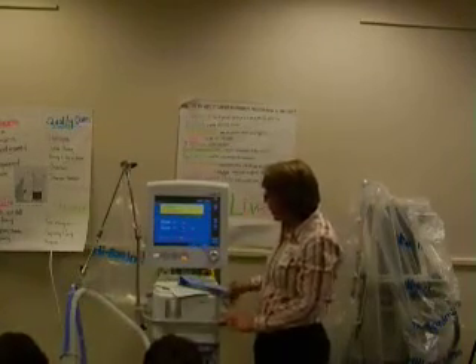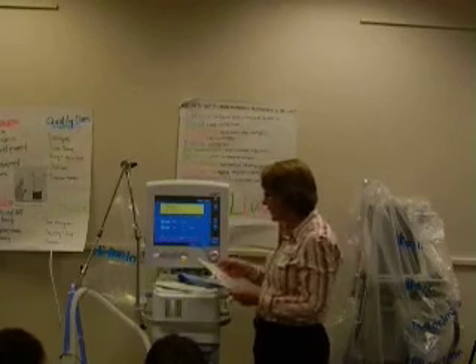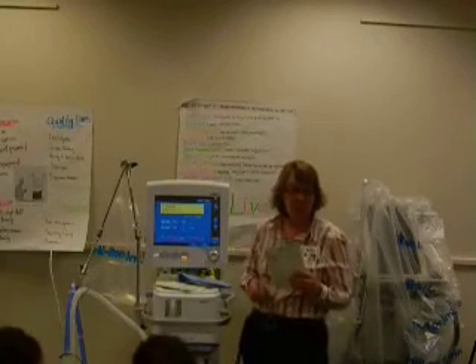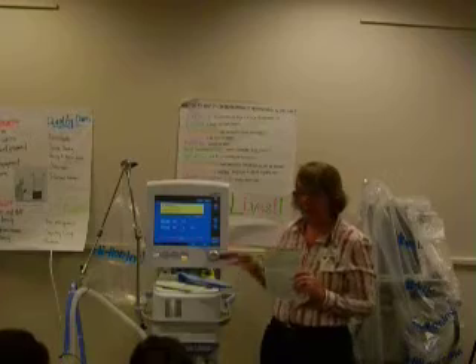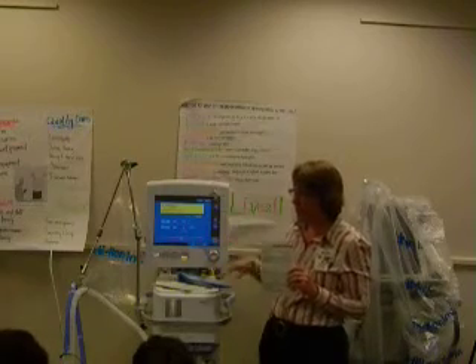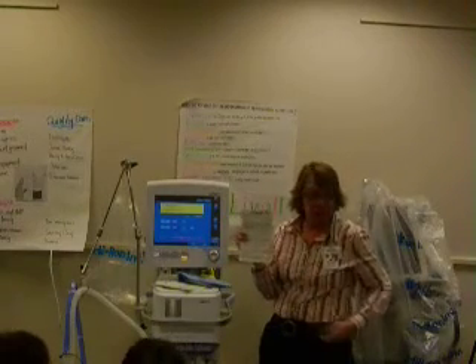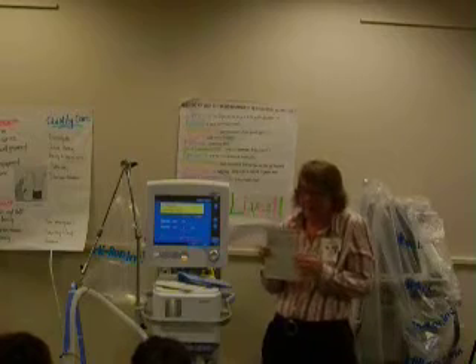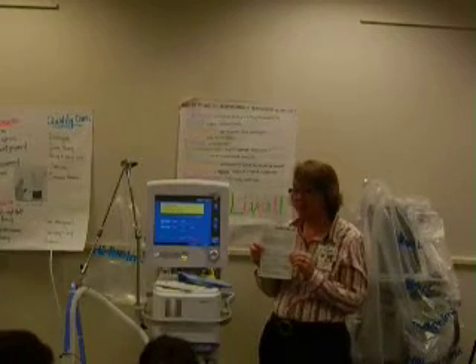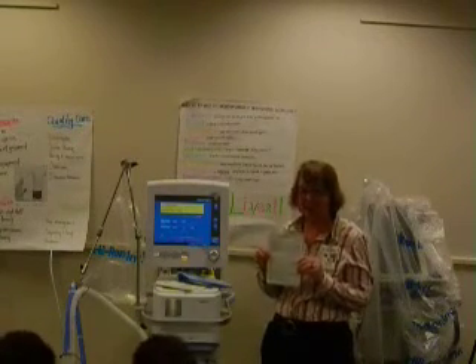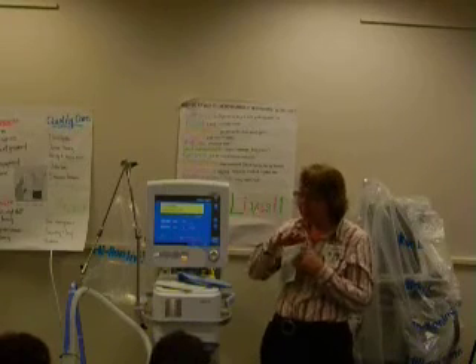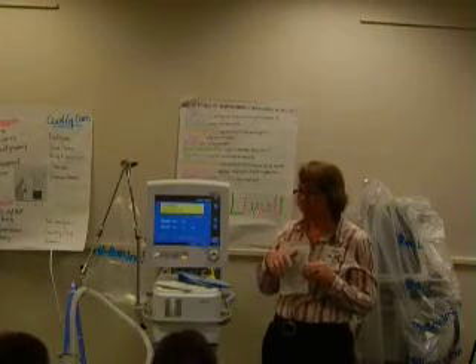The calibration on this one is different than the other ventilators because it's a little bit more old school. All the other ventilators have some steps that they guide you through on the ventilator. This one you've got an old card. This is how we used to always do it in the old days. It takes you step by step through the calibration and testing of the different things. Literally, we block the airway to check for high pressure alarms.